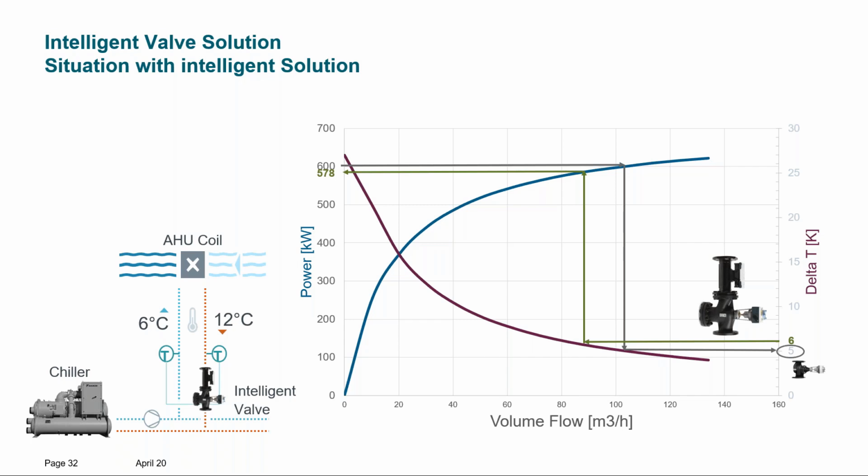And there is also an increase in the delta T. What you see is that the comfort level, or the energy transmission level of the coil, is not highly influenced by this reduction of the volume flow, but it is slightly influenced. Clearly, it goes a little bit back on this curve, but the curve is very flat in these full load conditions. So it's going back only from 600 kilowatt down to 578, which is a reduction of 3%. What does this 3% mean in regard to temperature? Because energy is what we distribute, but finally we would like to control comfort for the people. What would it mean?